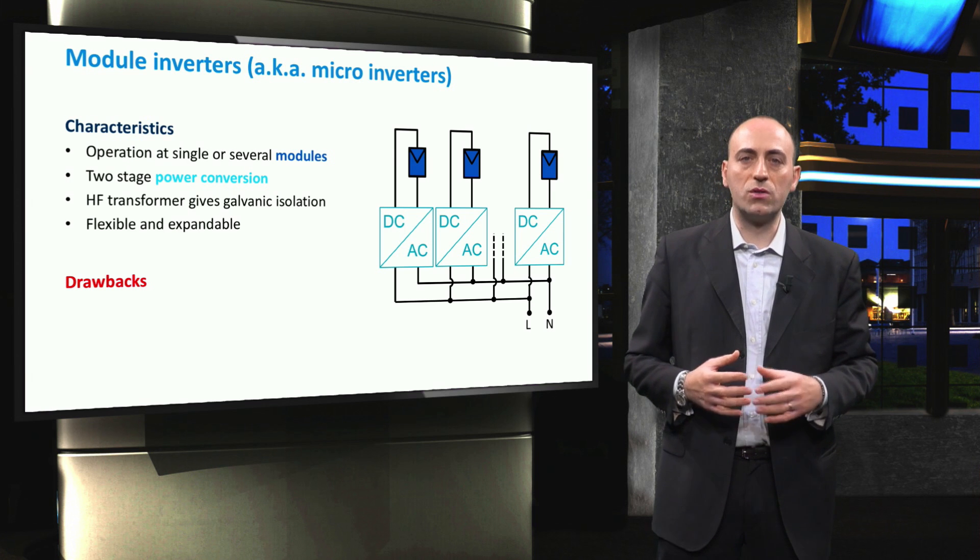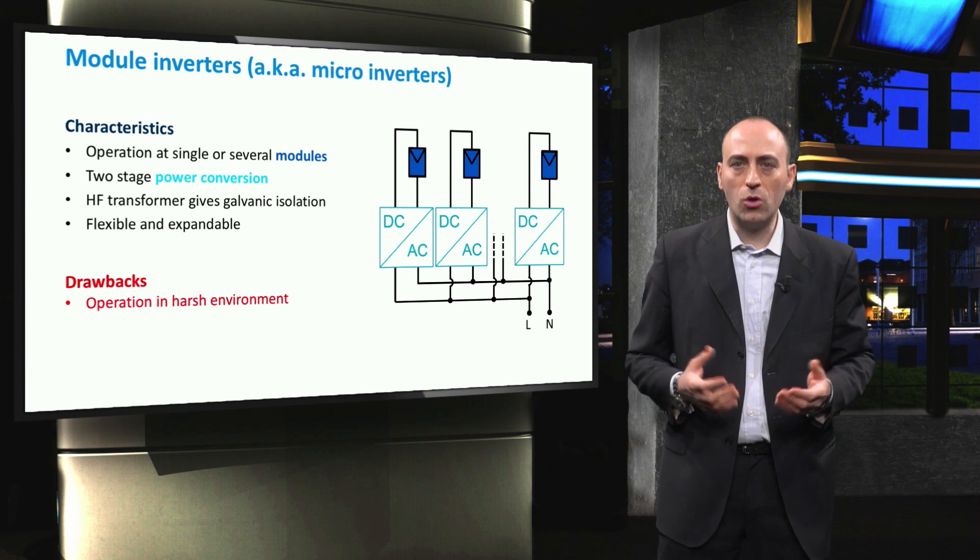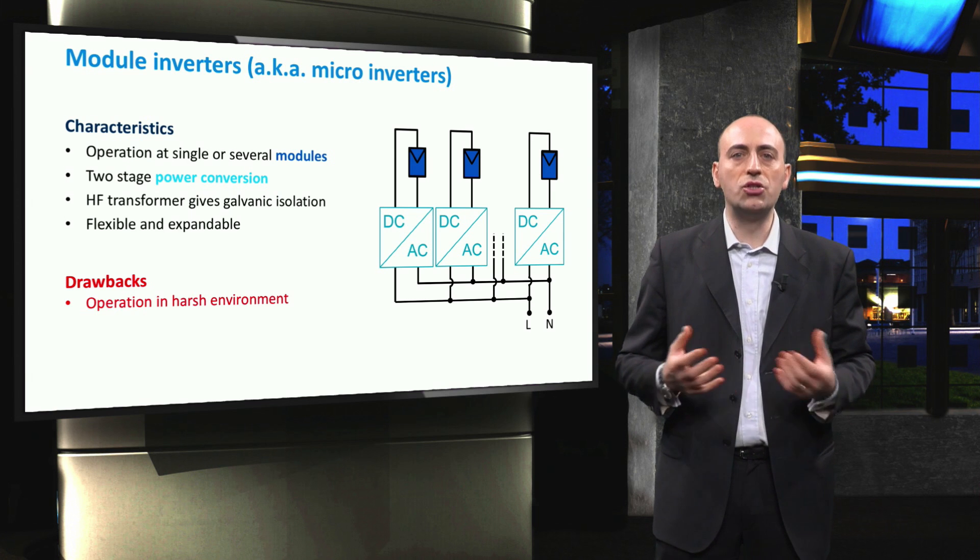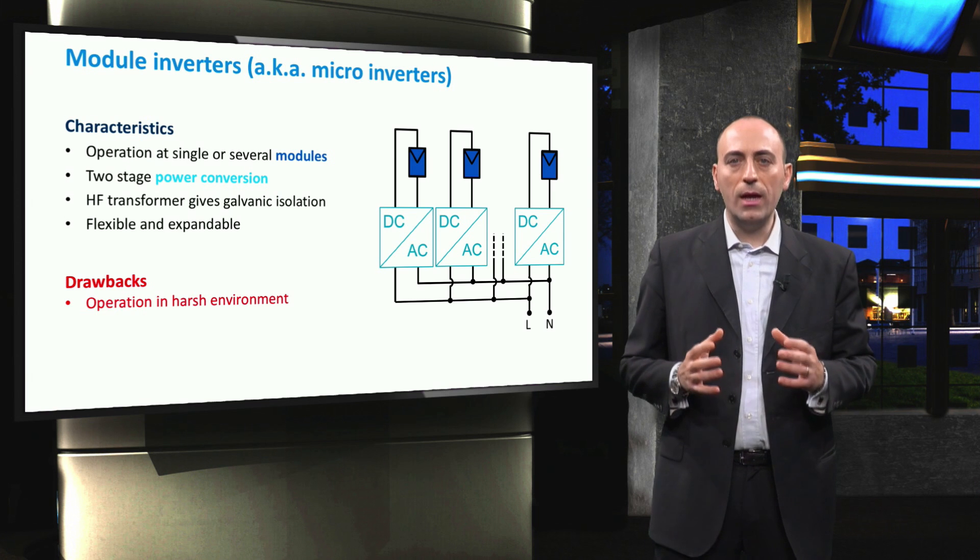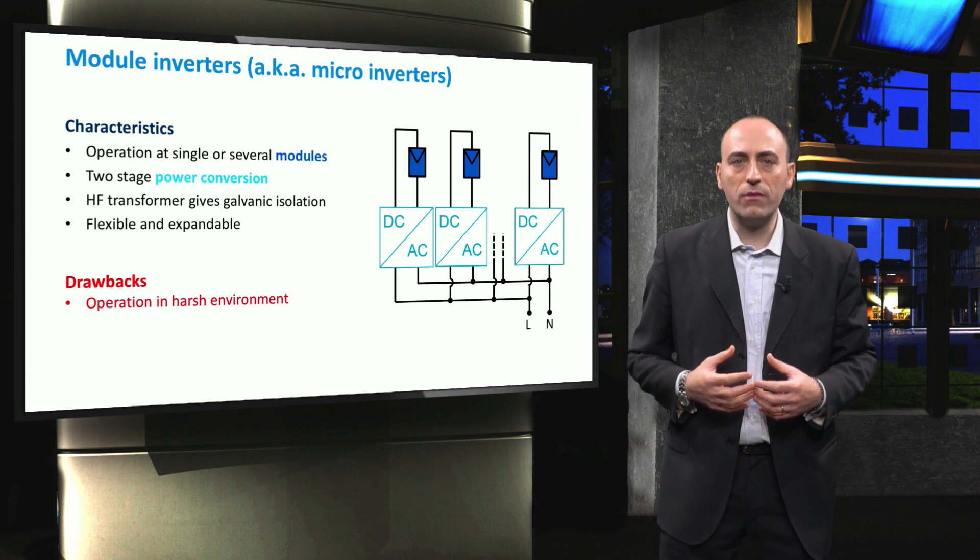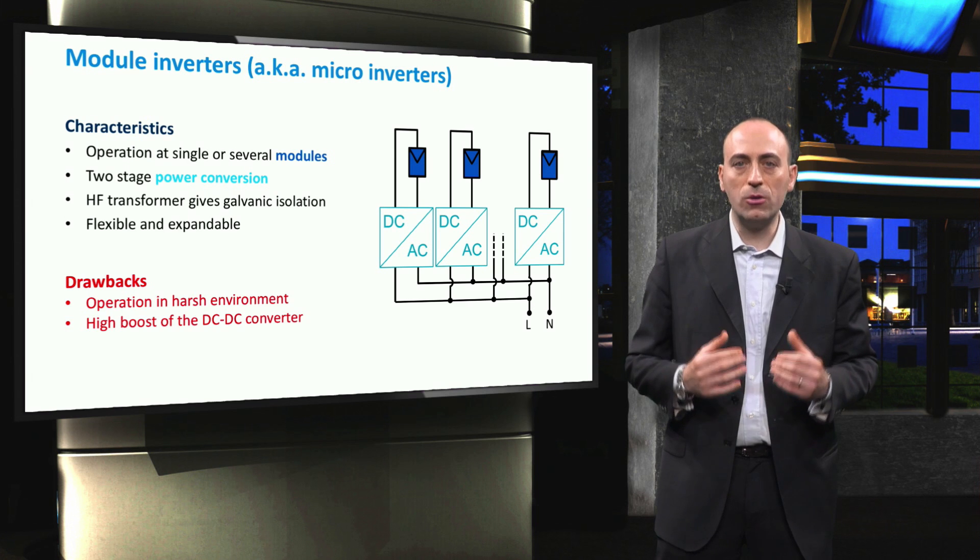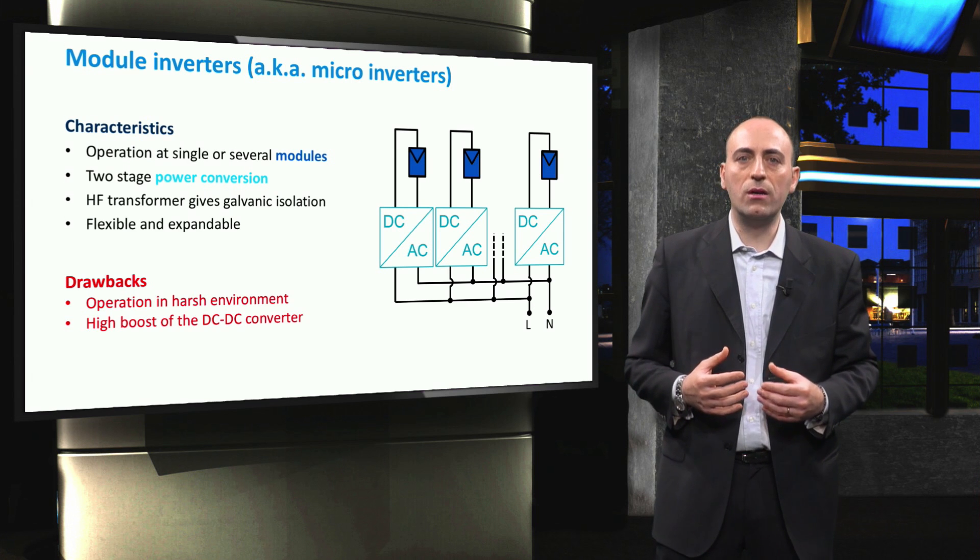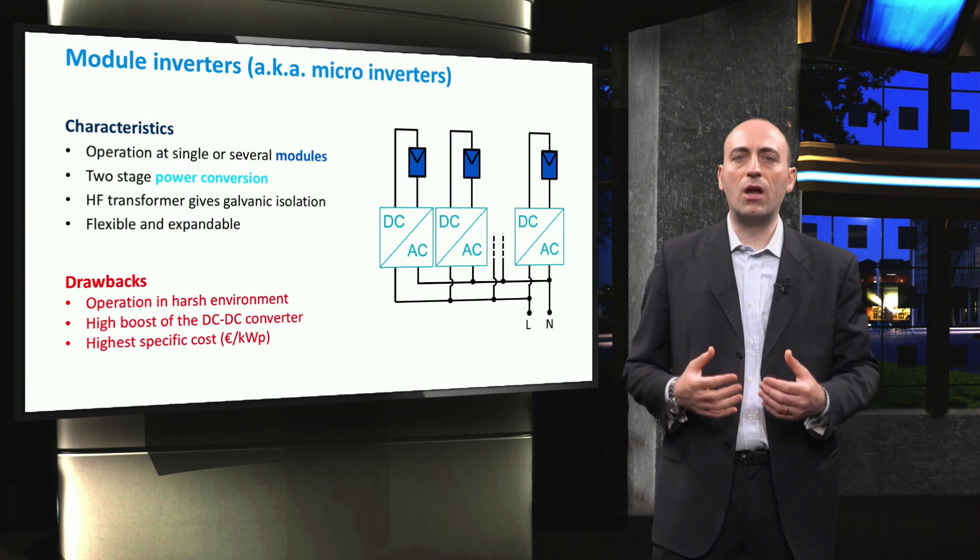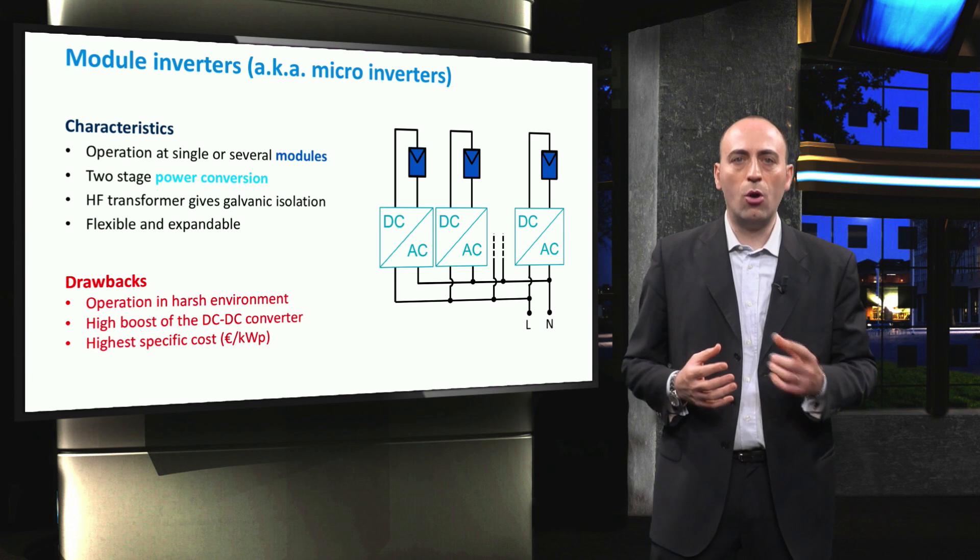Let's now see the drawbacks of such a system, because all these advantages come at a price. Since these inverters are mounted on the backside of a PV module, their embodiment has to be very sturdy in order to operate in harsh conditions, such as high temperature and large daily and seasonal temperature variations. Again, special attention should be put on safety issues related to cabling, to avoid that animals bite the cables, resulting in conduction failures. Another disadvantage is that the PV module voltage is much lower than the output AC voltage. Therefore, the DC-DC conversion has to be considerably boosting the voltage, and this has a detrimental effect on the inverter efficiency. Also, if you have a very large number of modules, then it is no longer economically interesting, because the specific costs are the highest of all the inverter topologies.